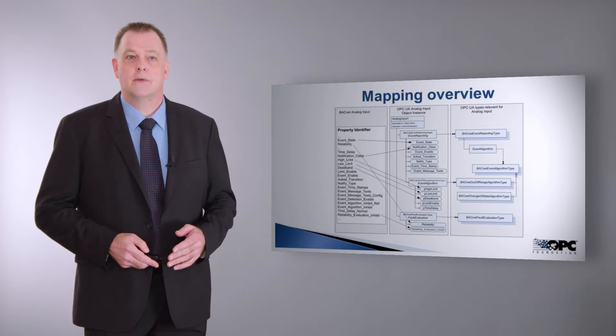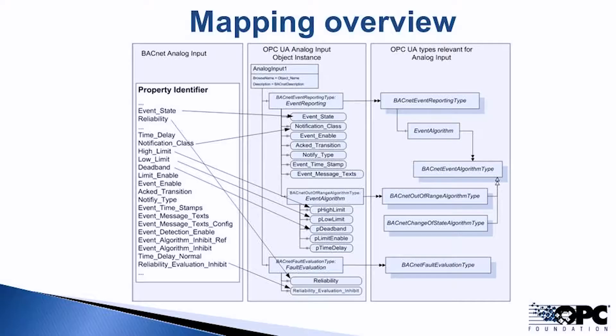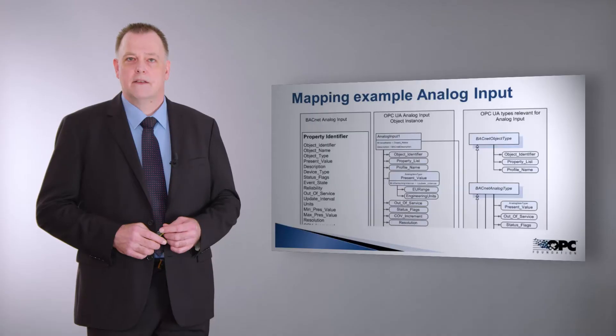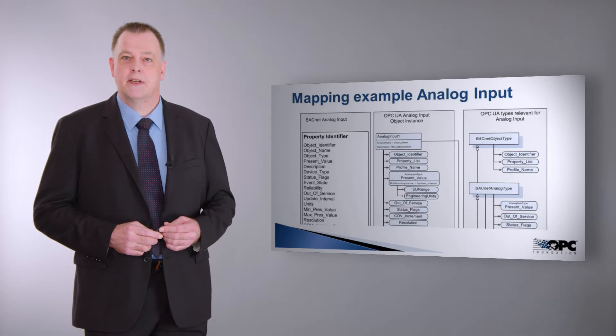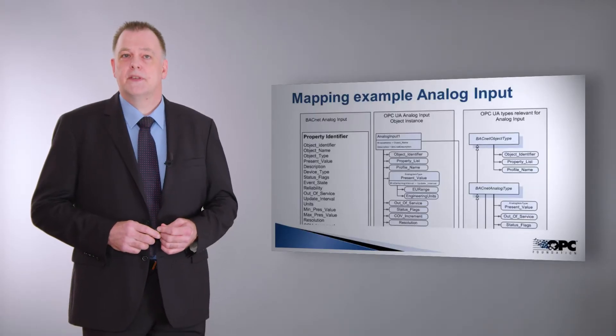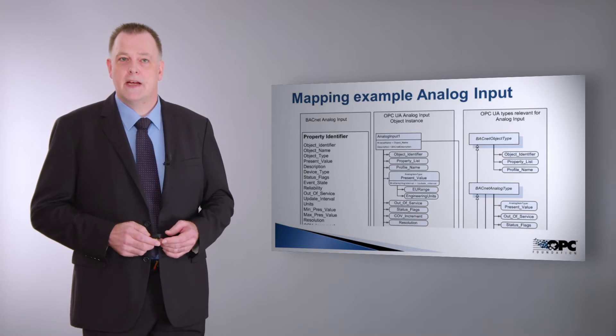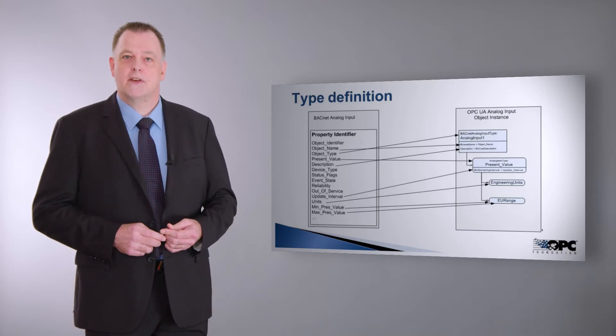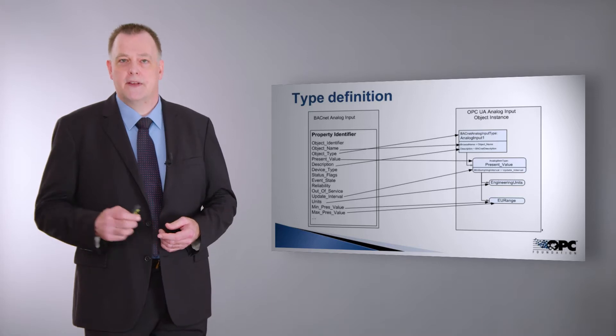This picture shows the overview of how to map the BACnet objects into OPC UA data structures. And in this picture the event and alarm properties are mapped into the OPC UA event and alarm data. OPC UA allows for type hierarchies and inheritance, and wherever possible we use these two features — which are actually not present in BACnet — to make it easier to derive from base data types. This picture shows how to map the information from a BACnet analog input object and its properties into the OPC UA types. We also specified specific types which are named BACnet followed by the type name, including type definitions not previously present in OPC UA.